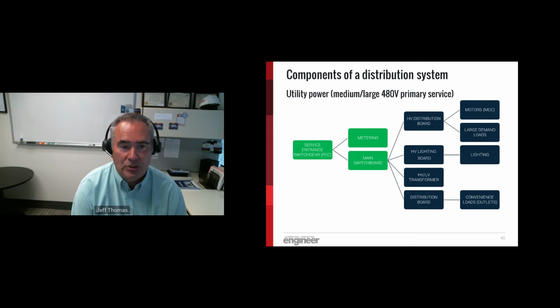Perhaps we've got a high voltage distribution board at the top there that feeds motors and large demand loads. Maybe we have large electric heat systems, as well as pumps and fans and so on and so forth. In the old days, actually in the not too recent old days, we would always have a high voltage lighting board because most of our lighting circuits were 277 volts, which would then be its own separate panel and be controlled accordingly. Then we would run into a high voltage to low voltage transformer, and this would knock us down and get us into the convenience outlet realm. The distribution board would be fed from that transformer and run all of our 120 volt standard receptacle loads.